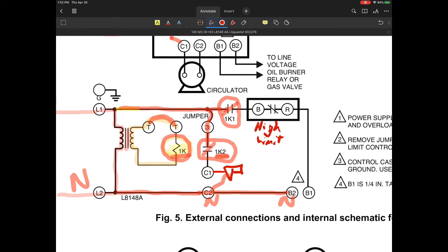Now, one thing I want to point out in the operation of this that's worth noting, and I'll come to the burner circuit later. You will notice that immediately upon a contact closure between T and T, which could be via a relay set of contacts that closes, or, if you had just a single thermostat, a thermostat closes and completes the path for T and T. Essentially, whenever we jumper this out or have a contact closure between the T and T terminals, you're really just completing this circuit from the transformer system and energizing the 1K relay. When the 1K relay gets energized, you'll also notice that between terminal 3 and 1K2 we are closing that, and immediately my circulating pump is energized.